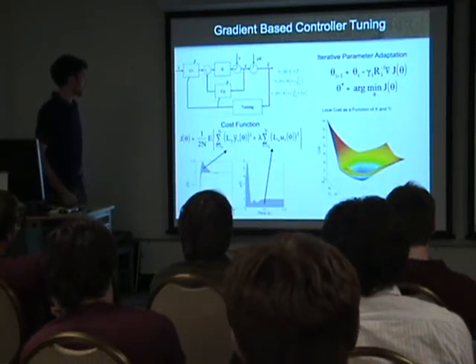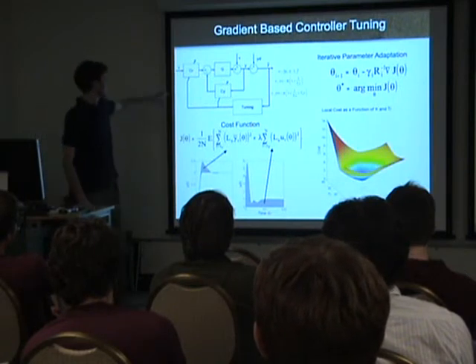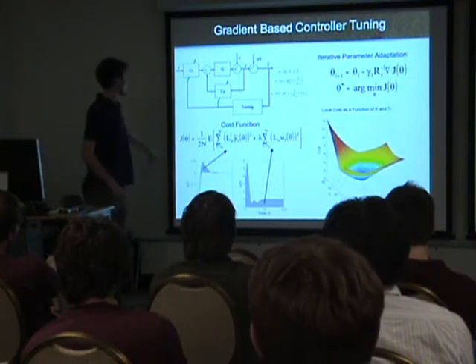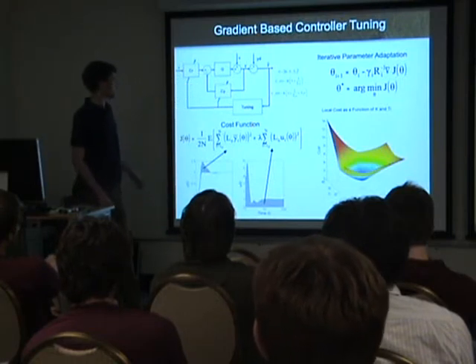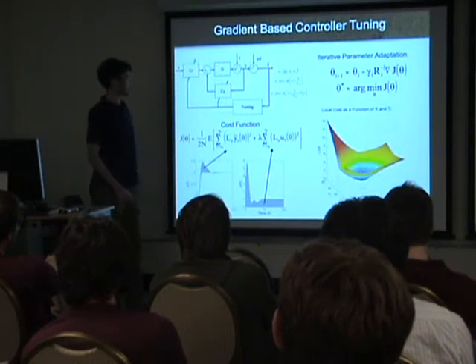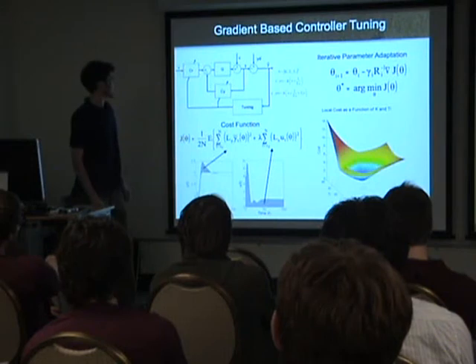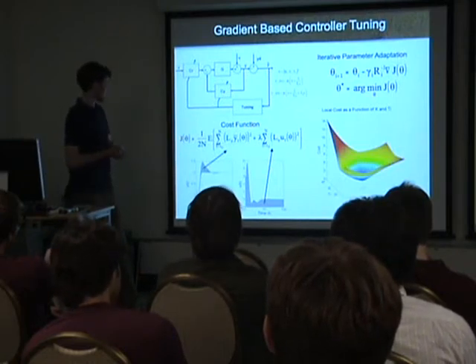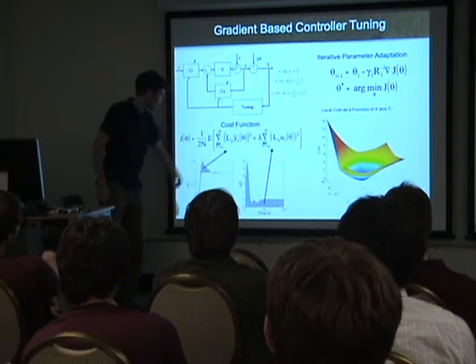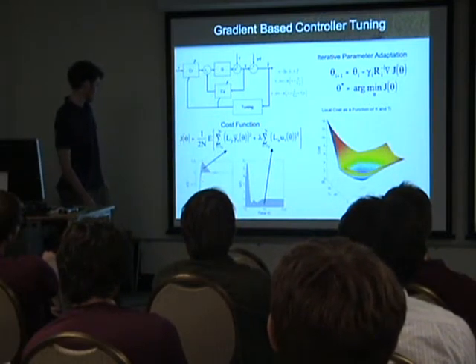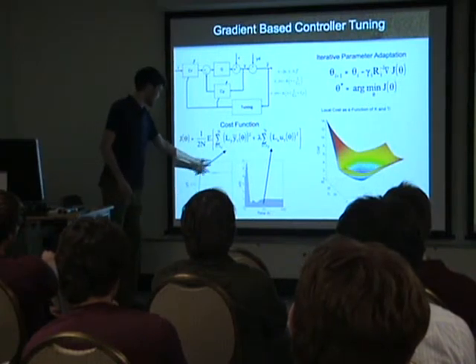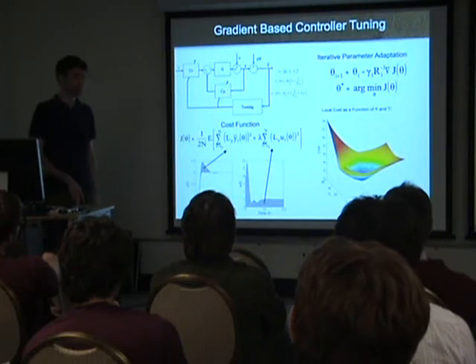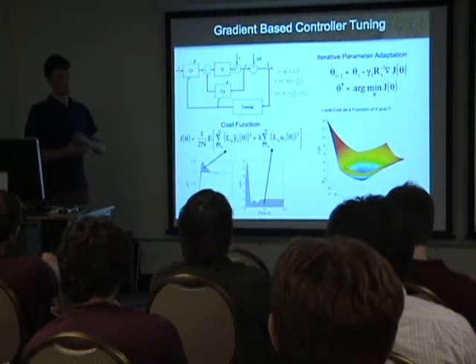The basis of it is our control loop: G is our plant, which is the thermal response of our heater profile, and CR and CY are in this case PI controllers. CR has moved beyond our summation block because we're trying to get rid of derivative kick, and then we're applying a tuning algorithm. The point of the tuning algorithm is to find the lowest cost of a cost function. The green line represents what we want — the response of what I believe is a fourth-order system — and the blue line is the actual response. The cost would be the integral of the area between the two, and you can play games with both the system response and the control effort to get the best cost overall depending on what you want to do.